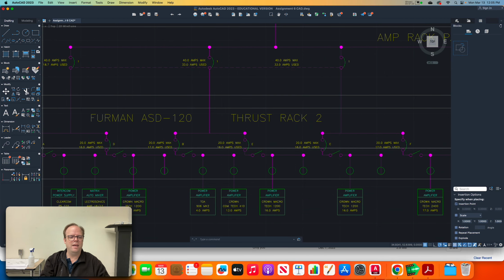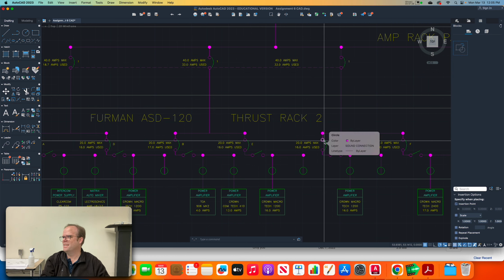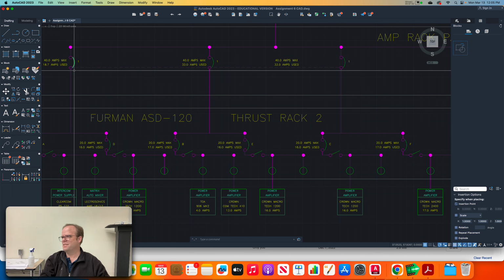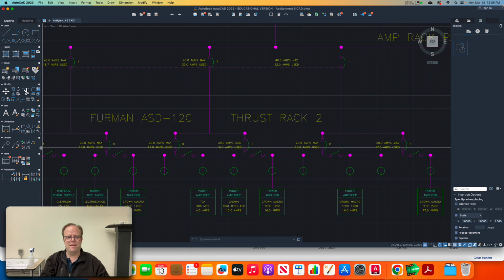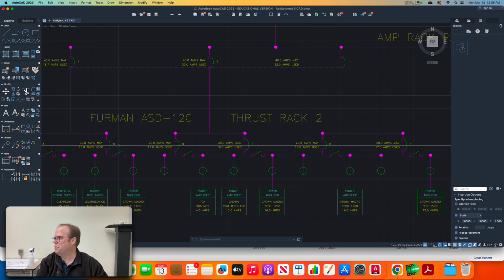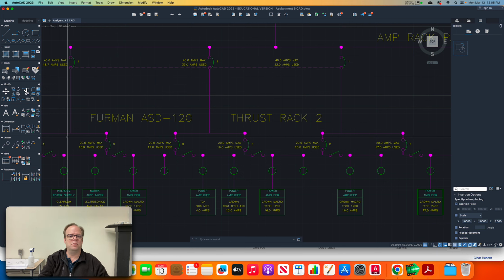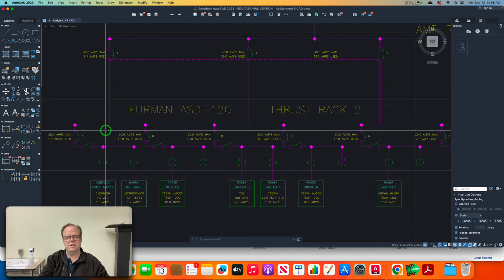So it goes A, waits a second, B, waits a second, C, waits a second, and then when it does D, D is turning on back at this first part, right? Because by then, A will have calmed down, and now hopefully we can turn D on and get its big suck, without tripping the whole thing. Okay, so that's how this is wired. So I've got them labeled out of sequence, and that's why.